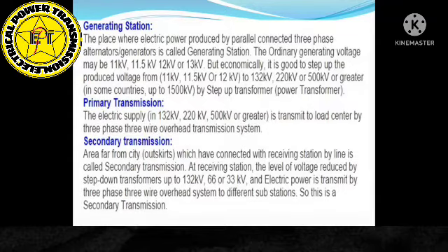So you remember again, either you are using 132, 220, 500, 66, 33, this is all through a three-phase, three-wire system. No fourth wire. A three-phase, four-wire system is valid only for the distribution system, and distribution, secondary distribution, even not for primary distribution of 11 kV.